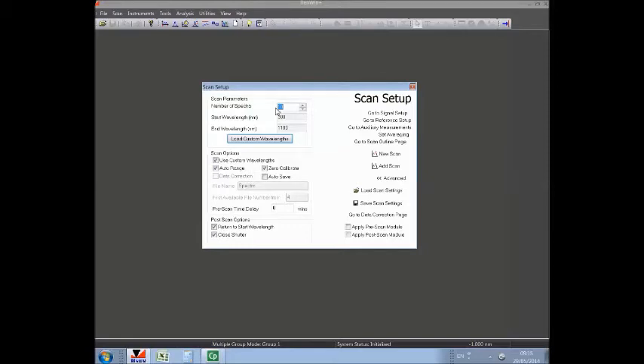Effectively, what I would prefer to do is to switch the lamp on, hit new scan for 10 scans, leave the system to do the measurements, come back some short time later, and delete the first 5 scans, for example, say this is the lamp warm-up time, and we can take an average of the remaining 5 scans to provide the calibration of the system.